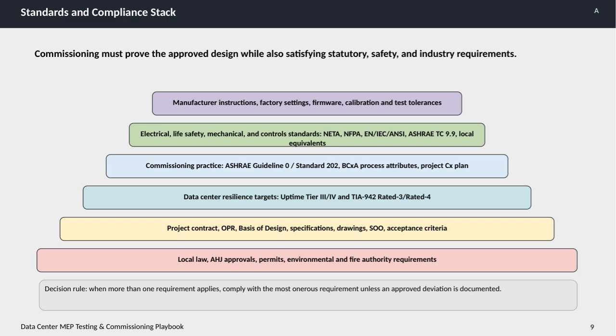The data center resilience targets are critical too, usually aligning with Uptime Institute Tier 3 or 4 standards and TIA 942 rated 3 or rated 4 classifications, ensuring high reliability and availability. Commissioning best practices are guided by ASHRAE Guideline 0, Standard 202, and the Building Commissioning Association's process attributes, supported by a detailed project commissioning plan. We also adhere to a variety of technical standards across electrical, life safety, mechanical, and controls disciplines, such as NETA, NFPA, EN, IEC, ANSI standards, ASHRAE TC 9.9, and relevant local equivalents. Manufacturer instructions are another essential piece, covering factory settings, firmware, calibration, and test tolerances. Finally, whenever there's an overlap of requirements, the rule is to comply with the most stringent one unless an approved deviation is documented. This ensures we meet or exceed all necessary criteria for safe, reliable, and compliant data center operations.